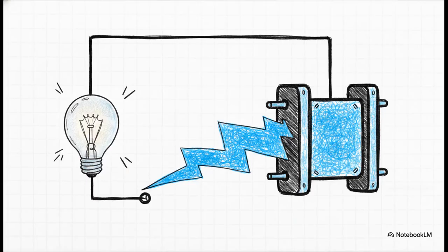So you might be wondering, why do we even need that external stabilizing resistor for high impedance to work? Well, it's all about physics. High impedance REF stays stable because it relies on a physical high impedance path. During an external fault, which is outside our invisible boundary, any slight mismatch current caused by minor CT imperfections is physically forced through that stabilizing resistor. And this resistor is often sized in the hundreds to thousands of ohms. The current goes there, instead of flowing through the sensitive relay operating coil. This hardware bypass is exactly what prevents false trips, without relying on any software compensation at all.